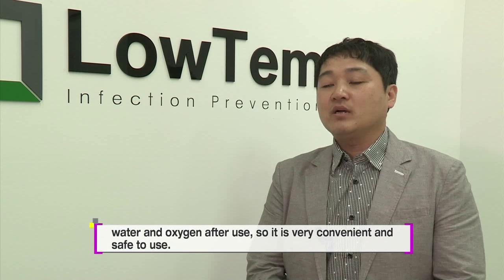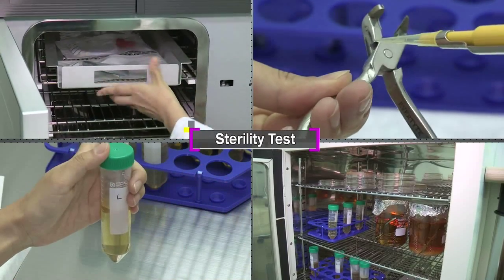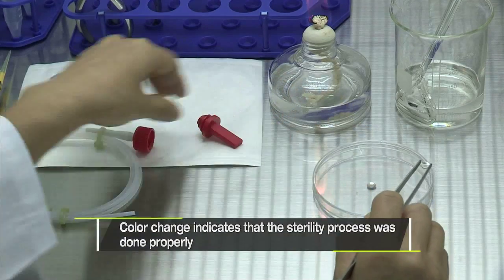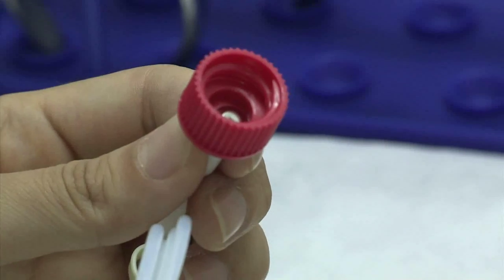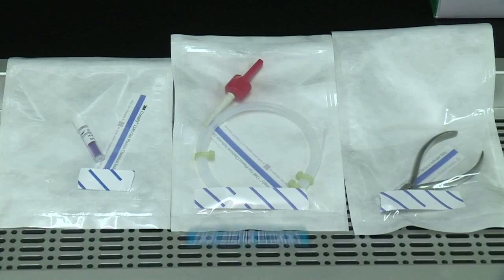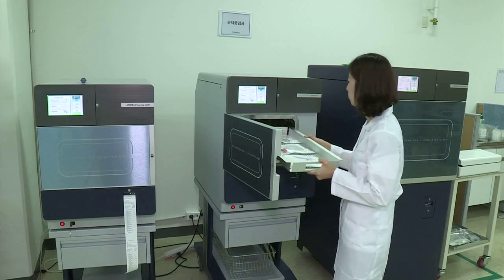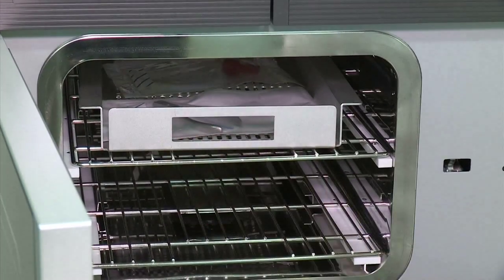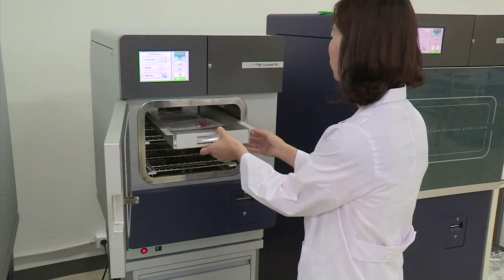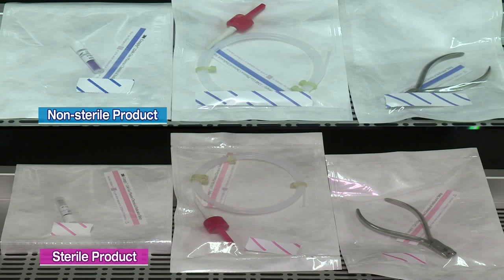They are preparing indicators filled with the culture medium in which bacteria can grow. PCD, which simulates the worst possible condition for the product that needs to be sterilized, is prepared to test the sterilization capability. Bacteria is directly introduced to the part of the tool where the parts come together, and it is placed inside LowTem's sterilizer. The sterilization process is confirmed through the touch LCD screen, and the process ends after about 40 minutes. The sticker turned pink to indicate that the sterilization process has been completed successfully.